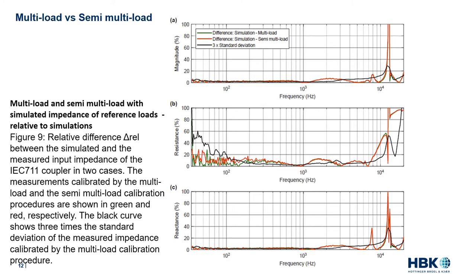Since the measured input impedance magnitude calibrated by the semi-multi-load and multi-load procedures has relatively small discrepancy compared to detailed simulations, and since the standard deviation of the multi-load procedure is small, these procedures seem to give a reliable estimate of the input impedance magnitude of complex structures such as the IEC711 coupler in the full audio bandwidth up to 20 kHz, and are expected to do so for measurements in real ears if other necessary precautions are taken.